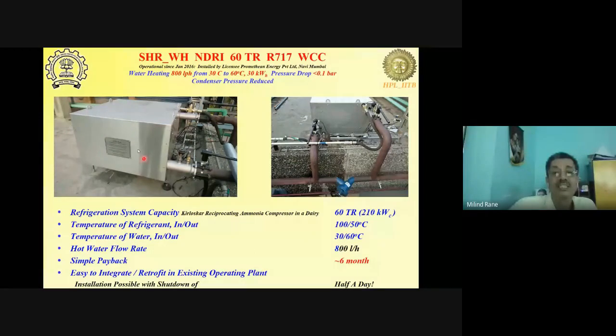These are some photographs of some of the units. In this particular heat exchanger, from a 60-ton ammonia refrigeration unit in a dairy, heat was recovered to heat up water from 30 to 60 degrees in a single pass. 800 liters was being heated. The payback estimated was around 6 months, and it took only half a day to integrate the system into the running plant.